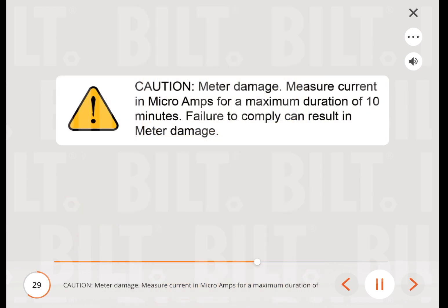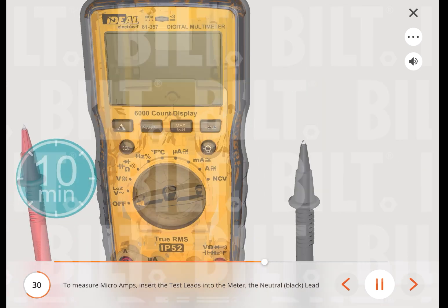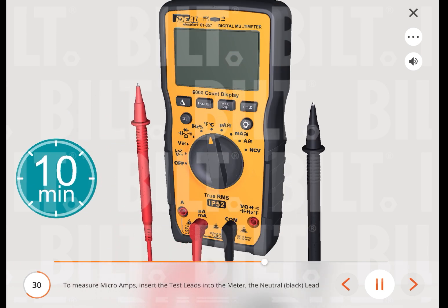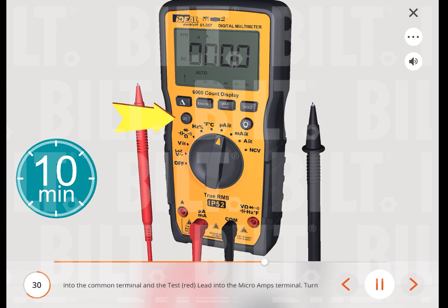Caution — meter damage: measure current in microamps for a maximum duration of 10 minutes. Failure to comply can result in meter damage. To measure microamps, insert the neutral (black) lead into the common terminal and the red lead into the microamps terminal. Turn the measuring function's dial to the microamps function, then press the select button to change the setting between DC and AC current.